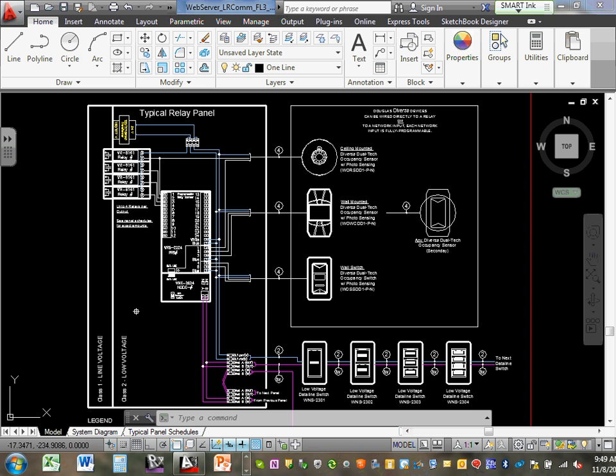Do you understand the purpose of the relay? Okay, the relay is a switch, right? It has the same functionality as that switch on the wall. What it does is let us break circuits down. So I have a single circuit coming that's going to feed 3 classrooms. What the relay does is have me break that classroom down into different switch sections. So if I'm going to switch these 3 rows independently, that takes 3 relays. Single circuit, right? But it gives me control of the circuit itself, so I can break it down into more usable loads. So I'm going to guess this building is 277 volt for economy, right?